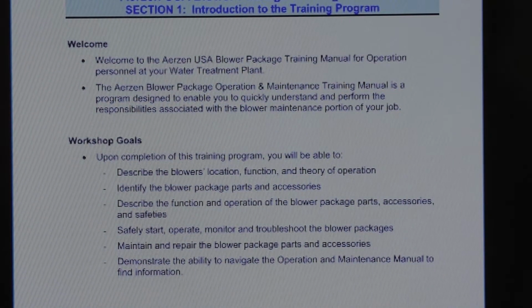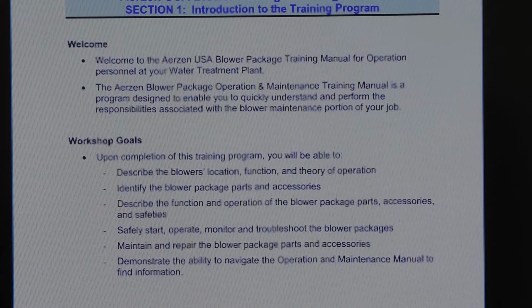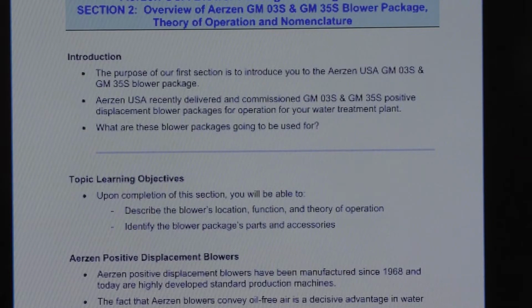You reset your maintenance counters at the HMI, the control on the unit. Your starting and stopping will take place for local at the VFD; remote or auto will be from SCADA. So go ahead and go to the next one.